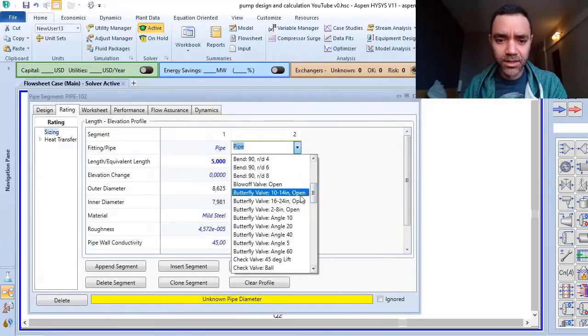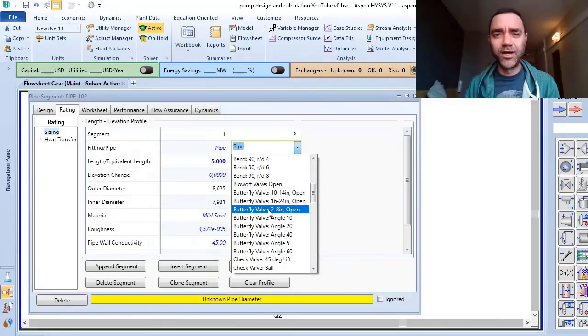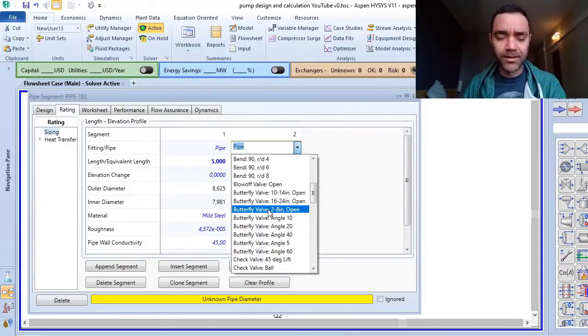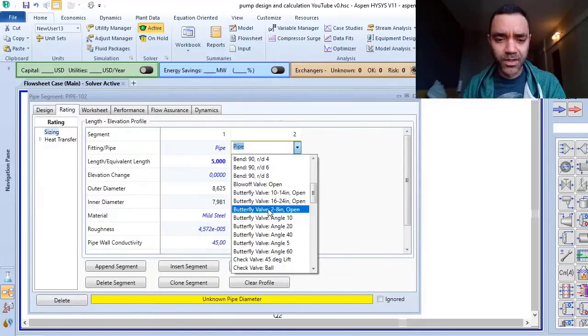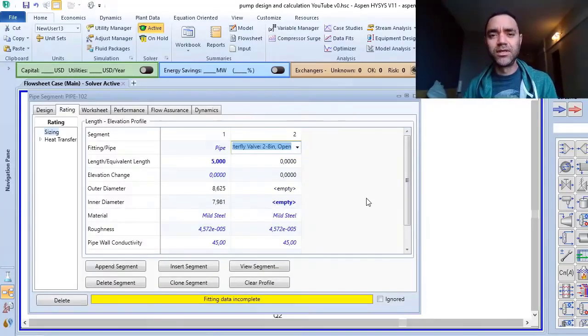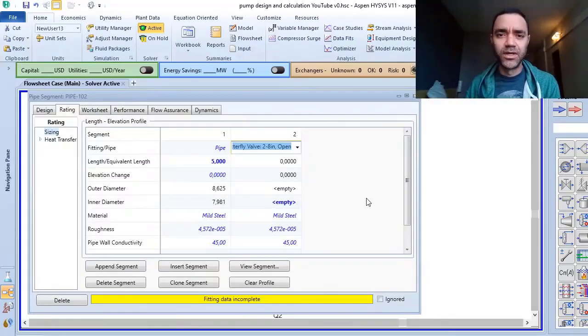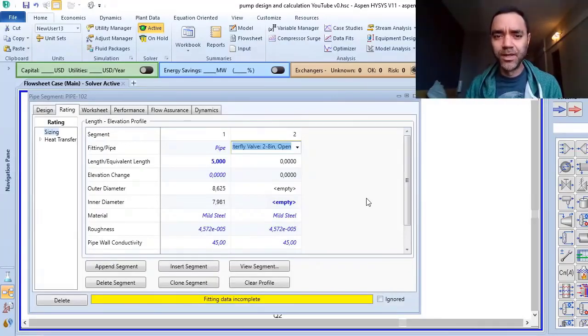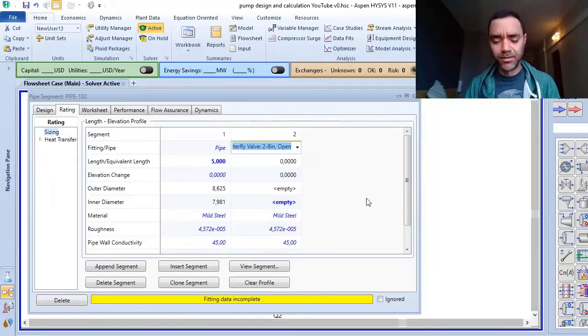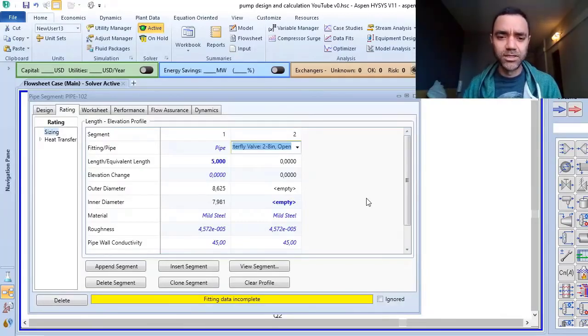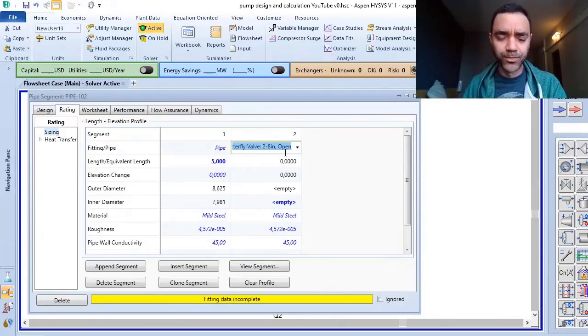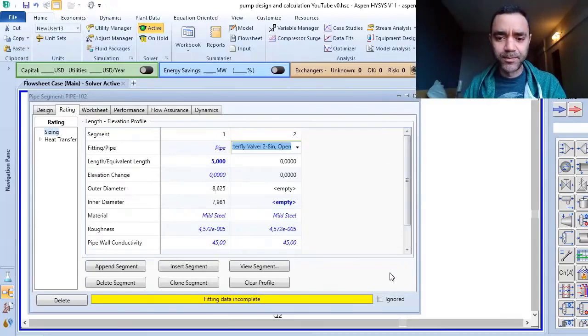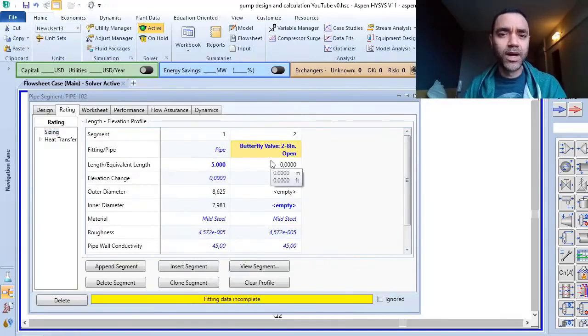I will consider a butterfly valve because the butterfly valve is cheaper, so usually we use butterfly valve instead of using a ball valve or instead of using a gate valve or globe valve. And as I don't want to regulate anything in the suction of my pump I will not use a globe valve because it adds more pressure drop. It is for, in many cases it is for regulation not for isolation, so just to add some considerations related to pressure drop in this pipe segment I'm using this butterfly valve.